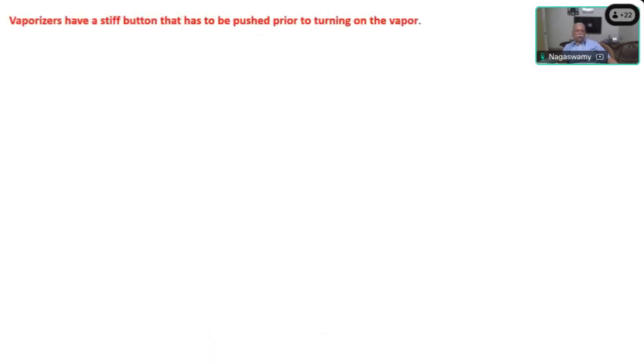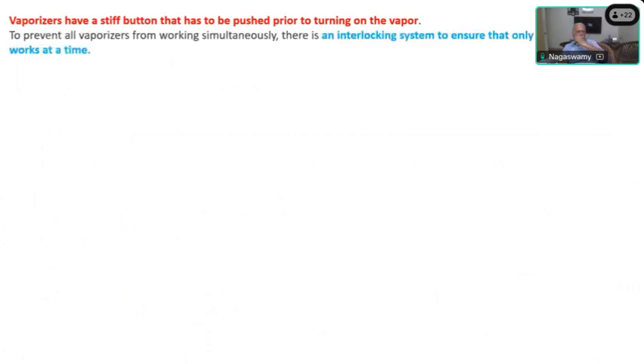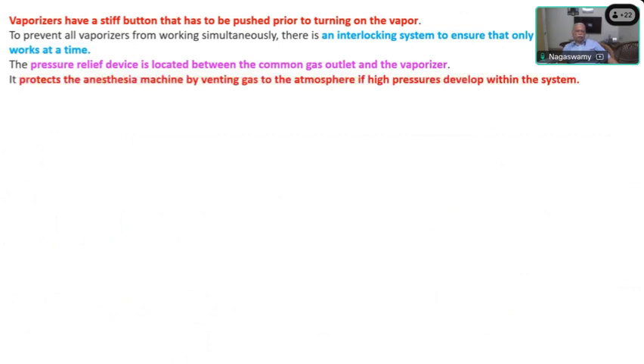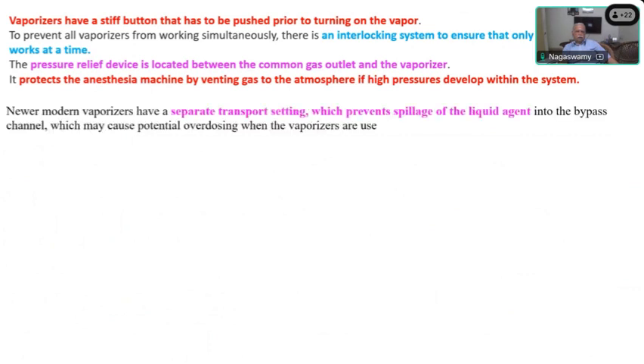Now, vaporizers have a stiff button that has to be pushed to turn so that they can be activated. This is again something like a lock, which is a safety feature. To prevent all vaporizers working simultaneously, there is an interlocking system at the back bar. And pressure relief devices are located between the common gas outlet and the vaporizer. Most of the machines have that. It protects the anesthesia machine by venting gases to the atmosphere if high pressure develops within this region.